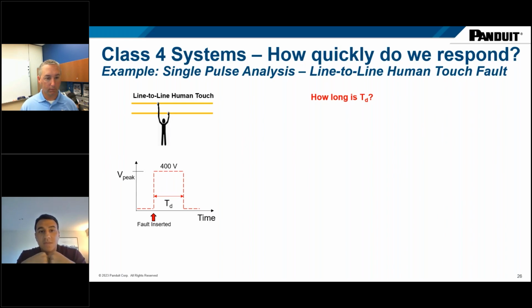Let's say I have a system that all it does is send a single pulse. The pulse looks like in the graph on the left here, and it has a peak voltage of 400 volts. And I'm trying to figure out for a line-to-line human touch, so someone might actually touch the 2 copper conductors, how long can this pulse last before it is unsafe? So that's what we're trying to figure out here.